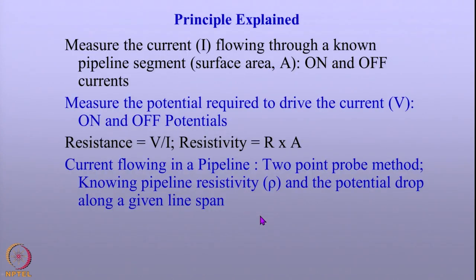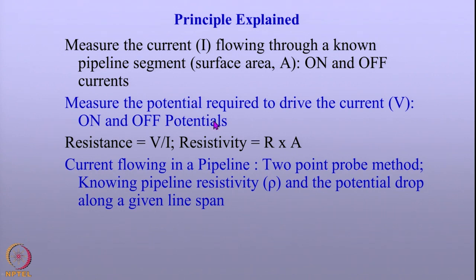If one has to measure the coating resistivity across a known segment of the pipeline — say about 4 to 9 kilometers — one requires a temporary ground bed to pass a DC current, connected to the pipeline through an interruptor. The currents passing along the pipeline at two locations are measured using potential drop with millivoltmeters. The pipe-to-soil potential at these locations is measured using a copper-copper sulfate electrode. The principle involved in measuring coating resistivity is simple: measure the current flowing in a known segment of known area, both when cathodic protection is turned on and when it is turned off.